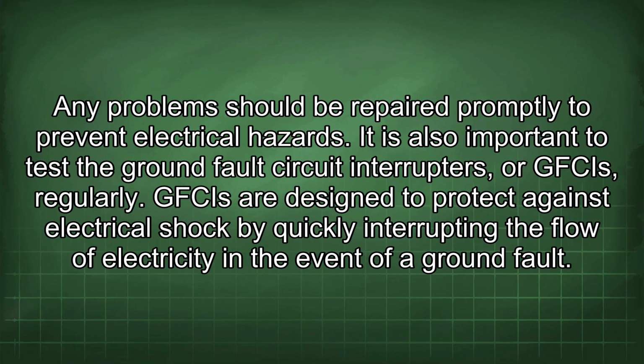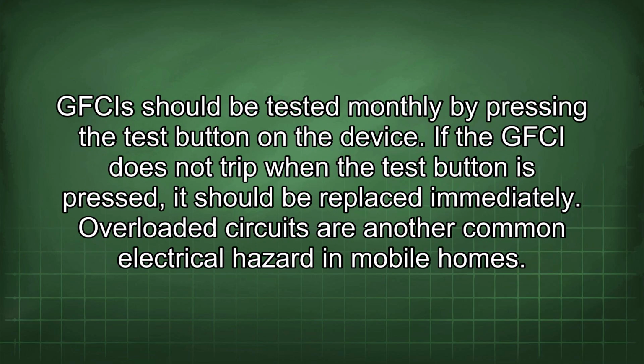It is also important to test the ground fault circuit interrupters, or GFCIs, regularly. GFCIs are designed to protect against electrical shock by quickly interrupting the flow of electricity in the event of a ground fault. GFCIs should be tested monthly by pressing the test button on the device. If the GFCI does not trip when the test button is pressed, it should be replaced immediately.